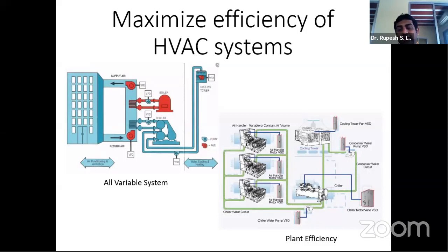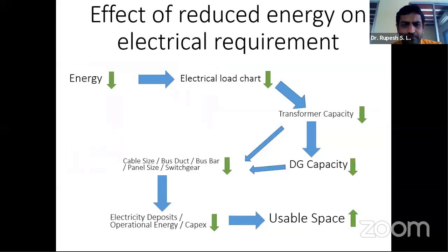So if you look at that, I think we have come a long way in the last 20 years or so, by bringing that 1.5 to 0.5 kilowatt per ton. And I think in the future, that is only set to go down. 0.5 kilowatt per ton was unheard of, because a chiller itself used to consume about 1 kilowatt per ton before. So zero energy buildings would have such plant efficiencies of about 0.5 or 0.6 kilowatt per ton. What is its effect on the electrical requirement?